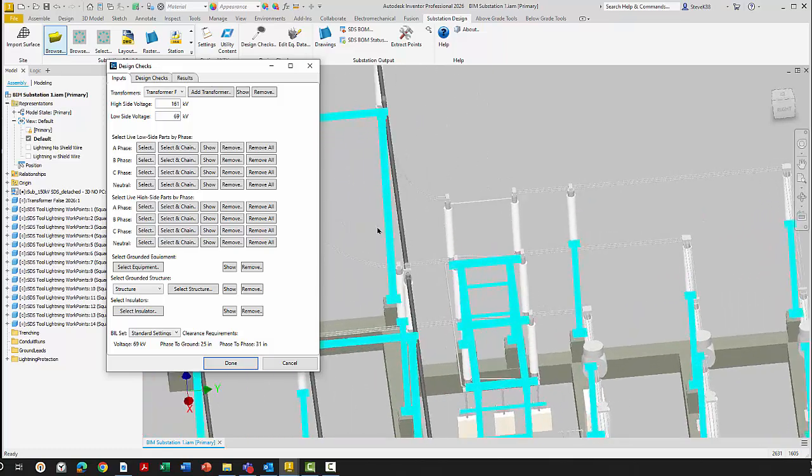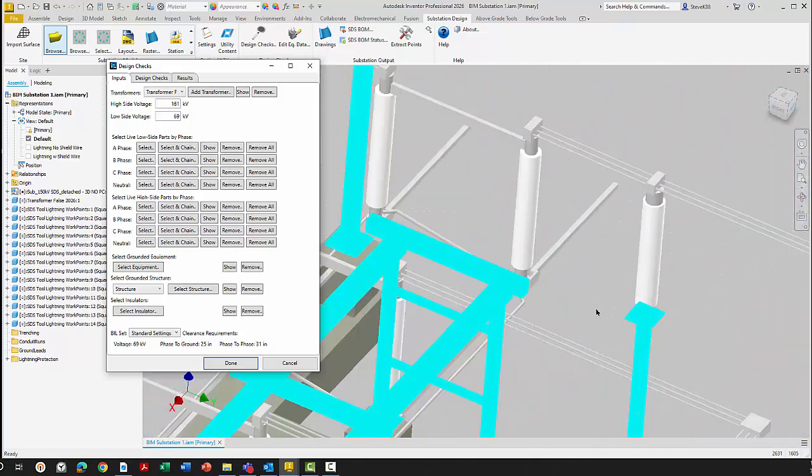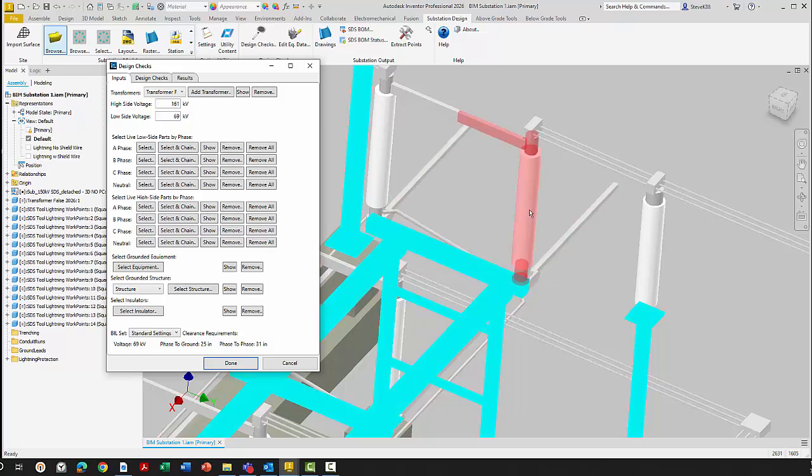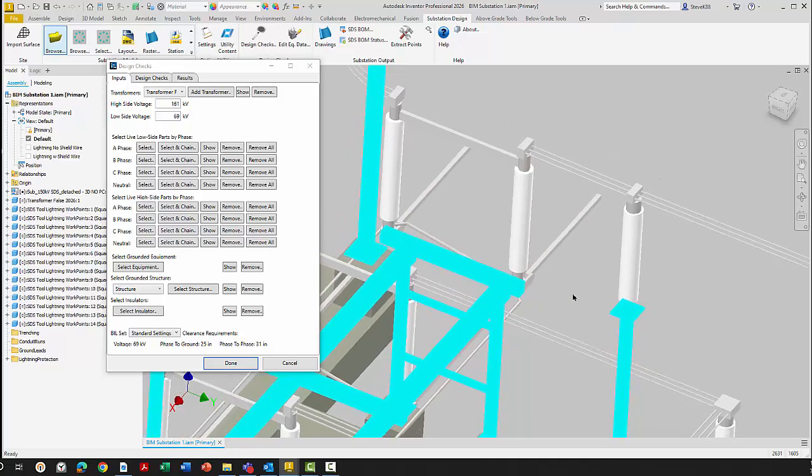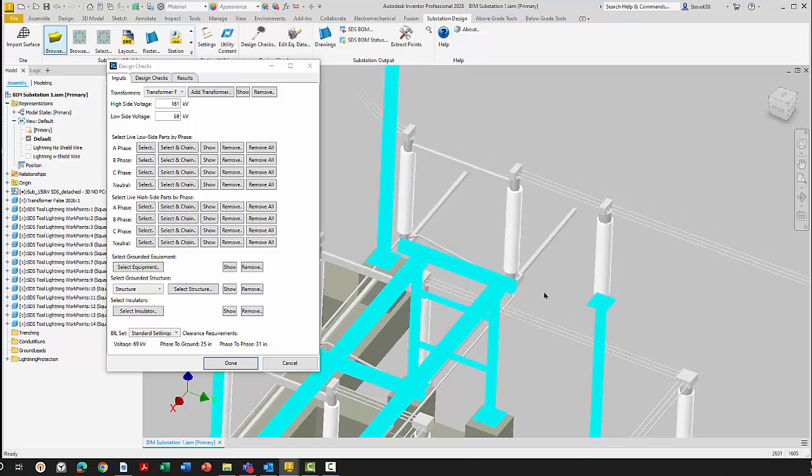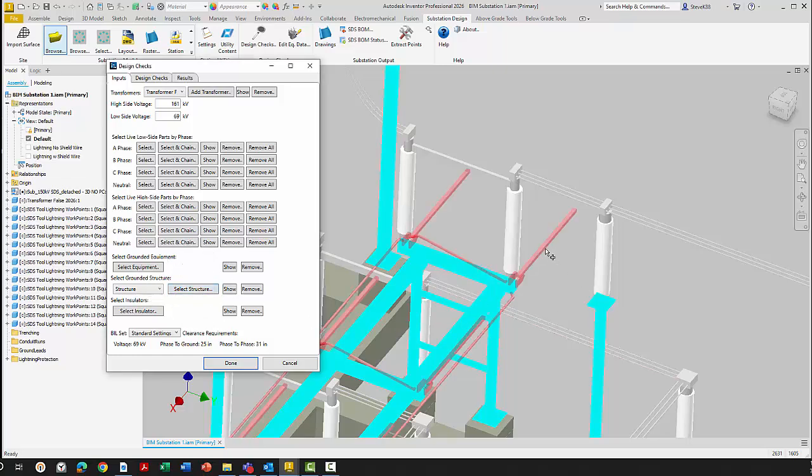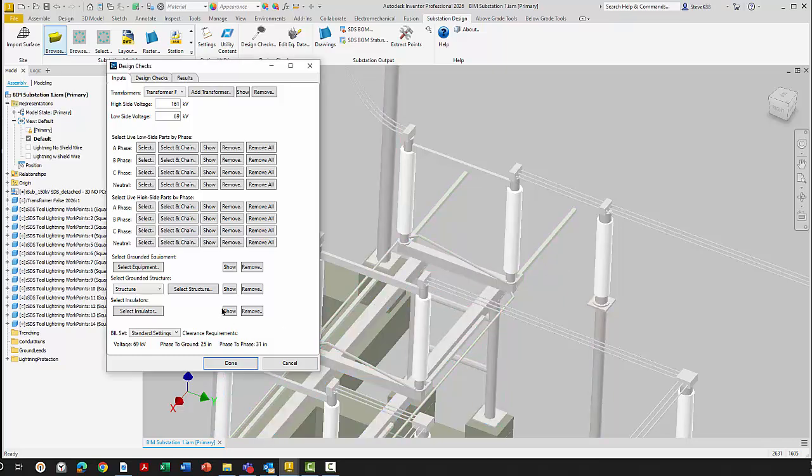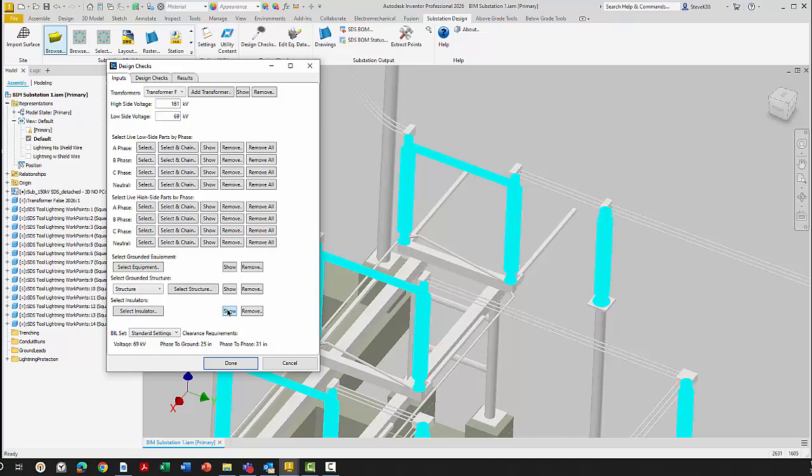If you look at the way the model was created, the structure is part of the base of the switch. So the switch doesn't have a base and they made that into the structure. That's an odd situation. The switch mechanism should be called a structure as well. When I say a structure, all the structure is grounded and considered a grounded item. So I'm going to say select structure, select this piece, and hit escape. And now that is structured and grounded. When I say something is an insulator, it's going to identify that as insulated equipment. Everything you see there is going to be identified as insulated.